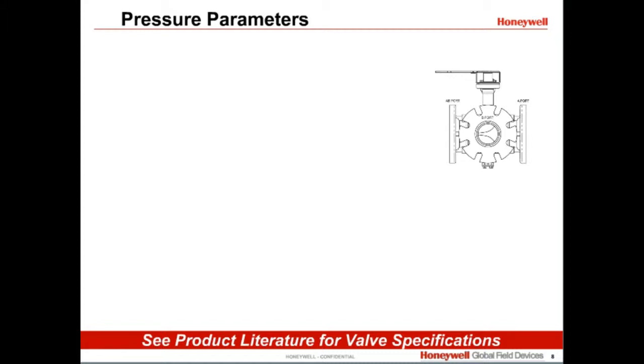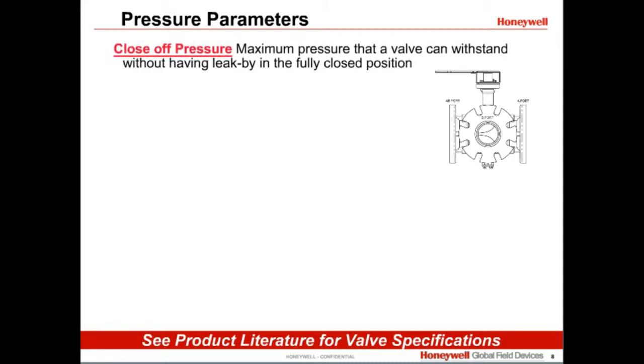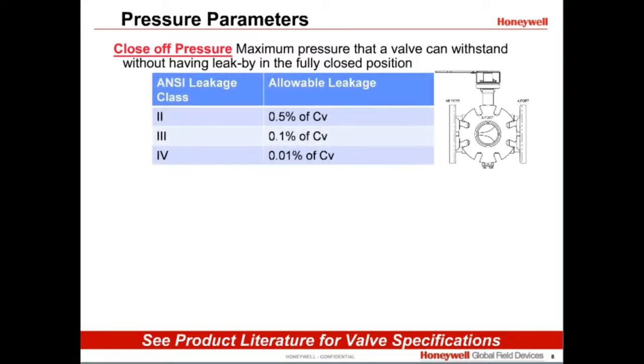The media in a system, of course, is under pressure. Because of this, it is an important consideration when selecting a valve. Here are 3 pressure parameters to consider. Close-off pressure is the maximum pressure that a valve can withstand in the fully closed position without exceeding the rated leakage. It varies from 50 to 130 psi depending on the valve size.